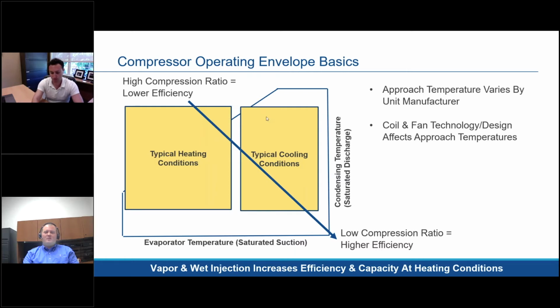Typically, the compressor is more efficient at low compression ratio conditions versus high compression ratio conditions. The compressor itself is doing more work, and the heat that it's generating causes that efficiency to go down as well at the high compression ratio conditions. But that's why vapor and wet injection helps quite a bit in these applications where you're really operating up in the top left side of the envelope itself.